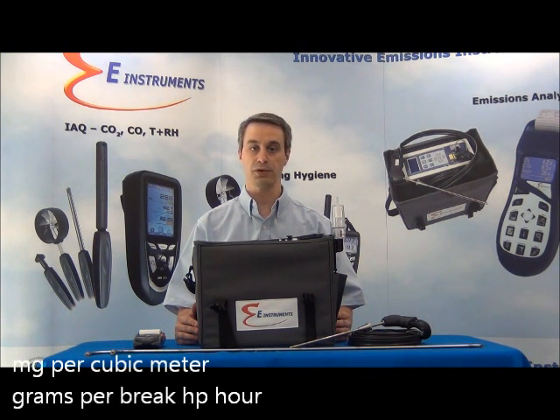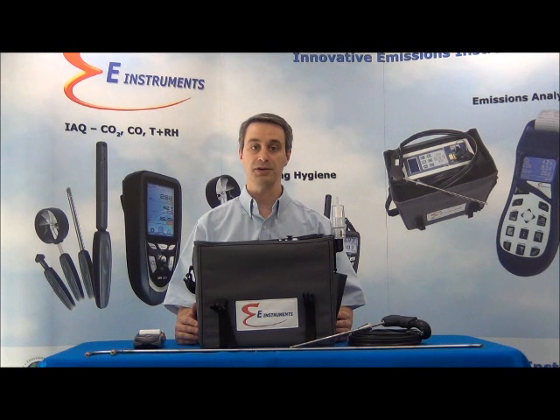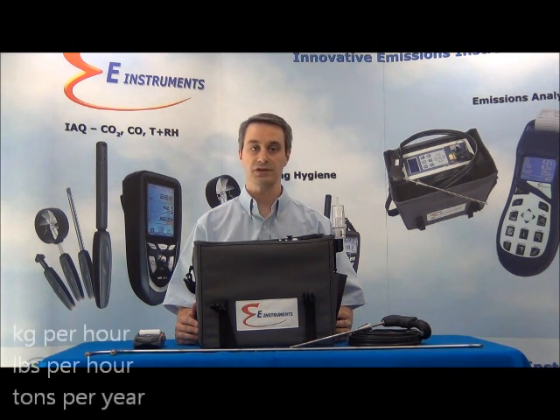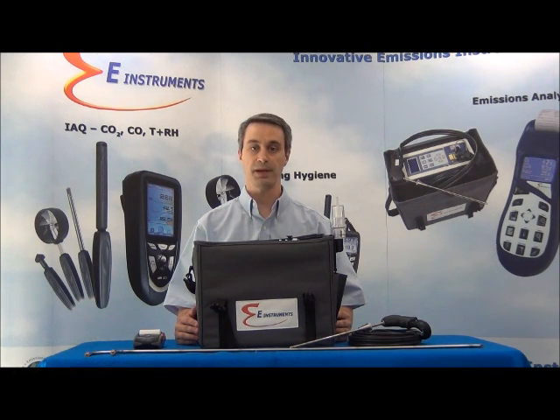Emissions are typically measured in units of ppm and percent, but they can also be expressed in other units such as milligrams per cubic meter and grams per brake horsepower hour for engine applications. Emissions can also be displayed in mass flow rate units such as kilograms or pounds per hour or tons per year if a pitot tube is used with the E5500 to measure stack gas velocity.